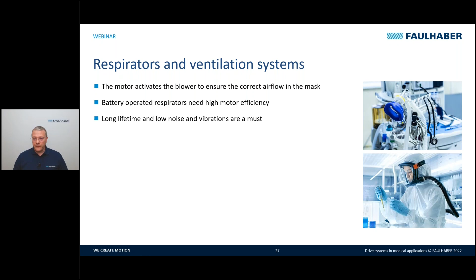Many respirators are also battery operated, so it's necessary to have a high efficiency of the motor, and it's required a very long lifetime and low noise and vibration in order to have a very reliable solution for the respirator and ventilator. For this reason, we have a DC motor with a diameter range from 15 to 22, like in this case. This is a 22 millimeter DC motor, very compact. High-speed ventilator needs a 2-pole brushless motor, for example, like this, in diameter 20 millimeter. And high-flow ventilator can use a flat brushless motor, 22 or 32 millimeter, also with integrated speed controller for a very compact blower.